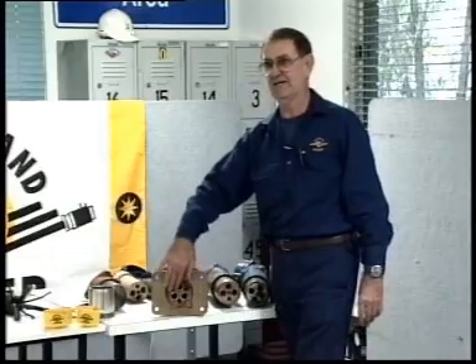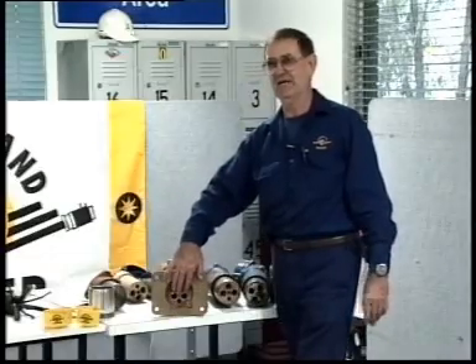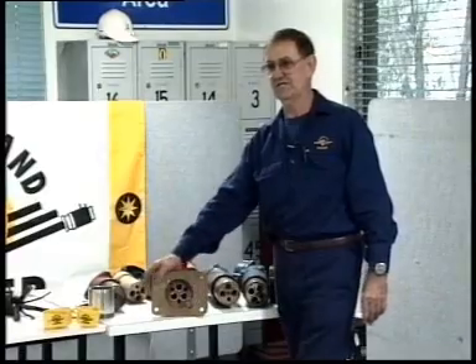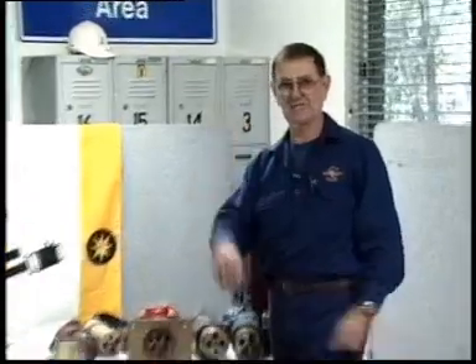We had a deputy, I think it was the year before last, at one of the mines, was closing an isolating switch, and he actually got his hand burnt because a fault occurred inside and the flame went out between the two surfaces and burnt him. And somebody said, well, I thought it was supposed to be cool enough so it didn't do that. And I said, hey, you wouldn't put your hand in boiling water, would you, which is 100 degrees C? And they said, no. And I said, well, obviously it was hot enough to burn him, but not hot enough to create an external problem.